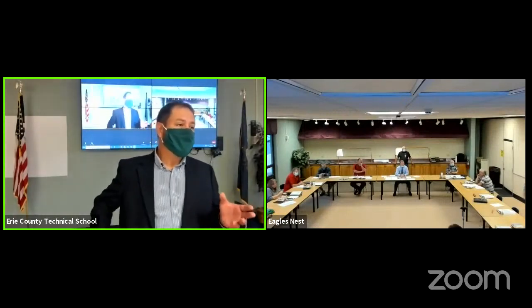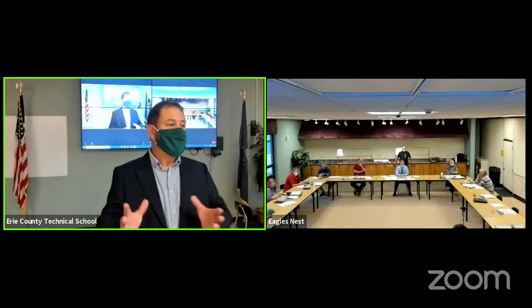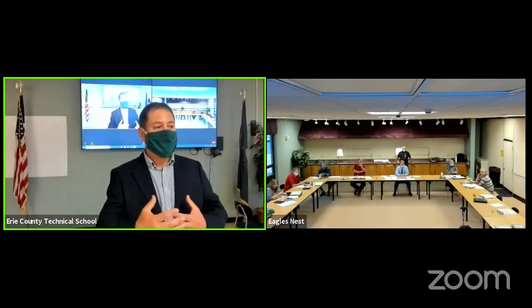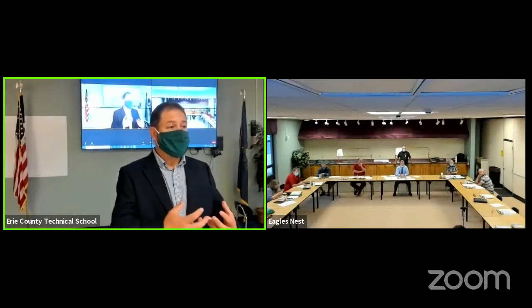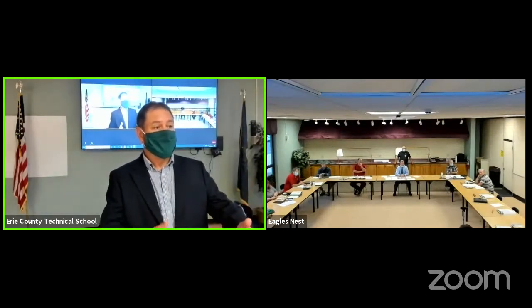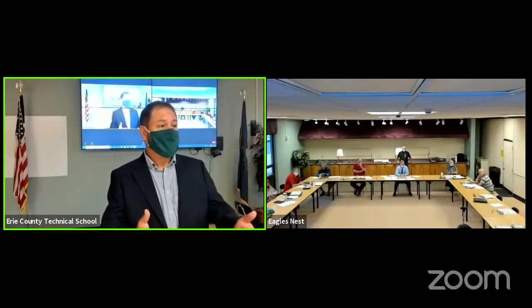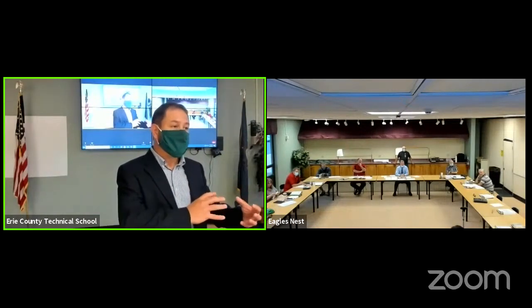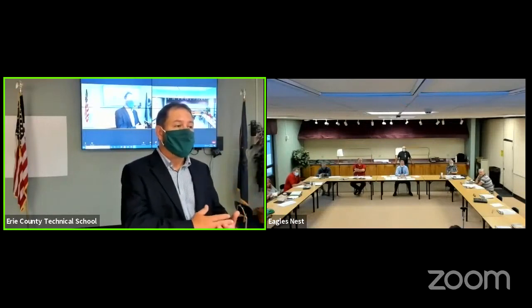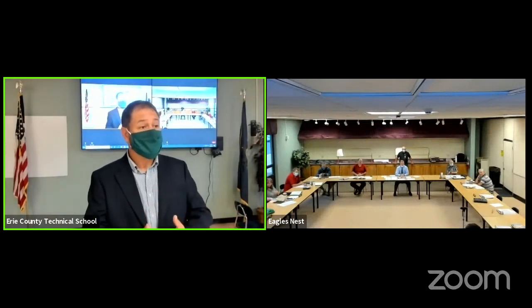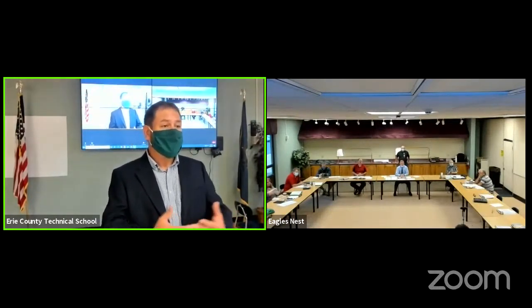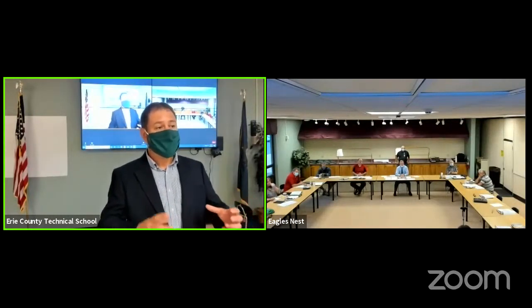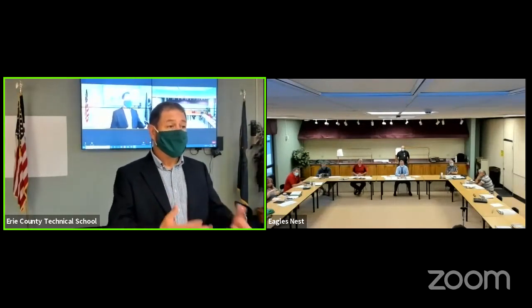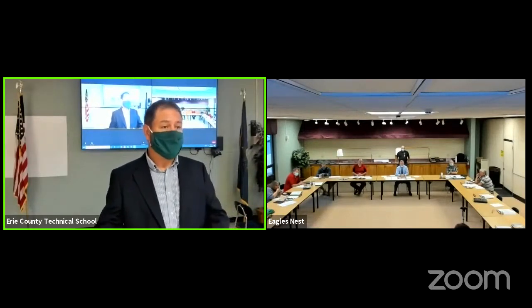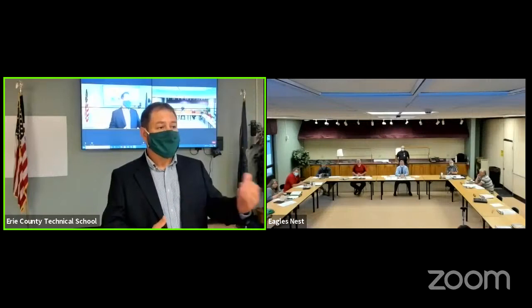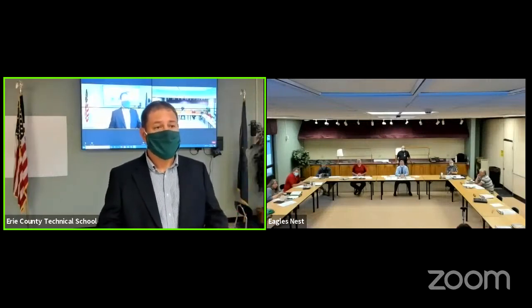We try to look at the hottest days on record for June or July, and that's most of the time what you size equipment for. We try to look at when you'll actually be operating, and some spare capacity just inherently comes with sizing the unit and the units available. Right now we're looking at 240-ton chillers. We may have looked at 230-ton, but it might not have been as close as we wanted to the actual load. So we don't feel it's oversized to the point of being ridiculous or that you're paying a lot extra. We do recommend that even if we went down to just the load you were looking at, still consider two chillers — because if one totally goes down, all the compressors lost, you could be sitting for months without any cooling. And even into September or the May-June timeframe, when you have students in, it can get fairly uncomfortable if you don't have something.